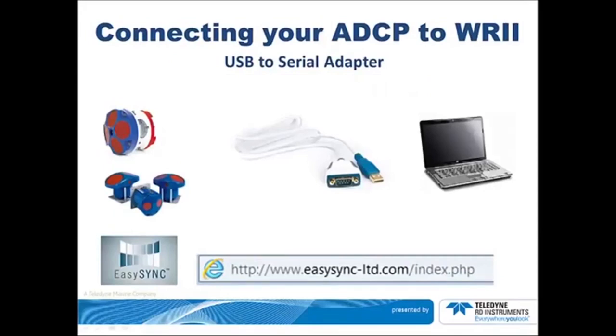Now we will look at connecting your ADCP using a serial adapter. We have found that the EasySync is a very good adapter, especially on Windows 7 laptops. You can use it to connect your Workhorse Rio Grande or Channel Master to your laptop. Driver installation instructions are included with the device, and at the bottom of the page you can see the web address.